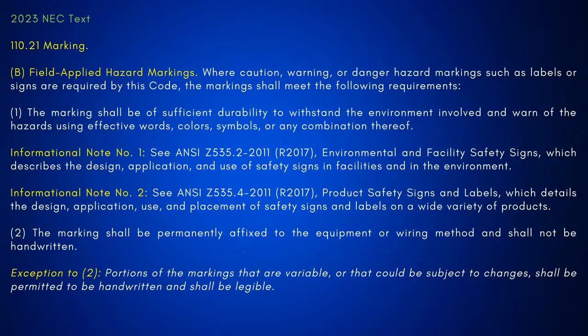And if you look at 110.21(B)(1) right here in the text, it tells you the marking shall be of sufficient durability to withstand the environment involved and warn of the hazards using effective words, symbols, colors, or any combination thereof. And that's what you get into. And then when you look at (B)(2), it has to be what? Permanently affixed to the equipment.